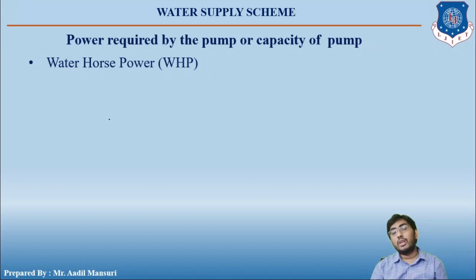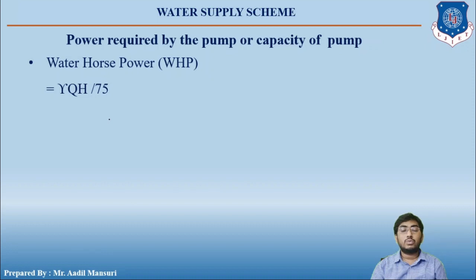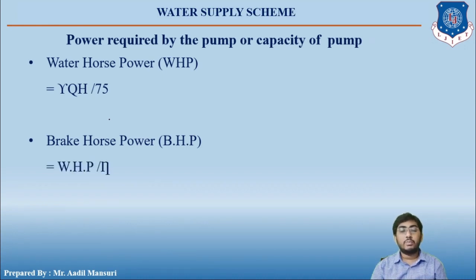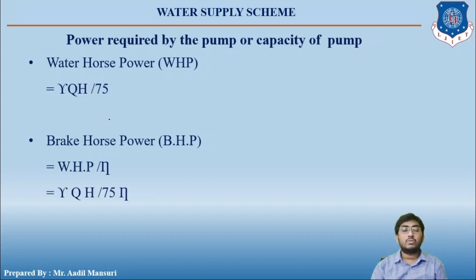The formula for water horsepower (WHP) is: WHP = γQH/75. If you need to find the brake horsepower (BHP), that equals water horsepower divided by efficiency: BHP = γQH/(75η).